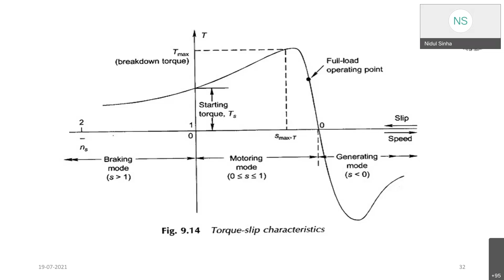Otherwise, you have to overspeed the machine - the turbine has to be overspeeded, the rotor has to be overspeeded. But there is a limit - theoretically one cannot go beyond 25% more than the rated speed. So the safer range is 10% or 15%, though theoretically more is possible.